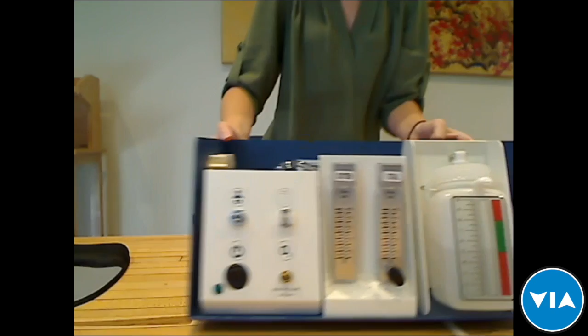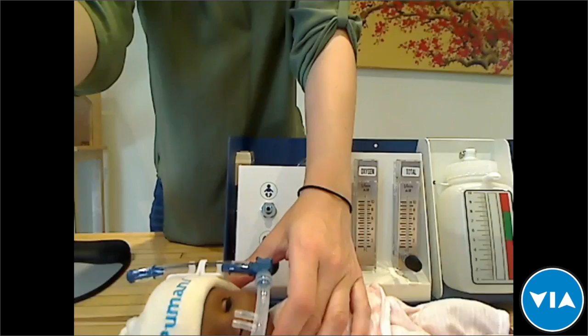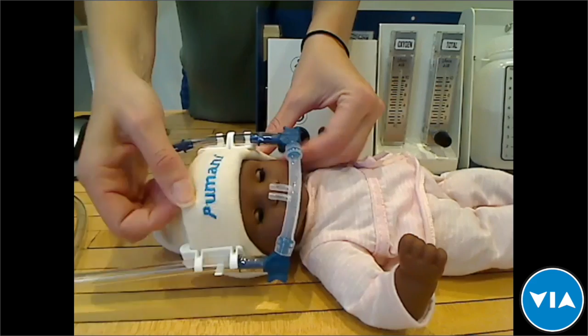Okay. And are there any spare parts or consumables that are single use and that you would recommend only single use? Yeah, the one item that we recommend really should be changed after each patient is the hat. I'll just demonstrate here on the doll. The hat is such an important component in keeping the tubing attached, so the tightness of the hat is really important. So we recommend that the hat only be used once per patient, so that this tightness is really secured on the baby, and you're not loosening the hat on multiple patients. That's the one component that we really think should be only one patient per use.